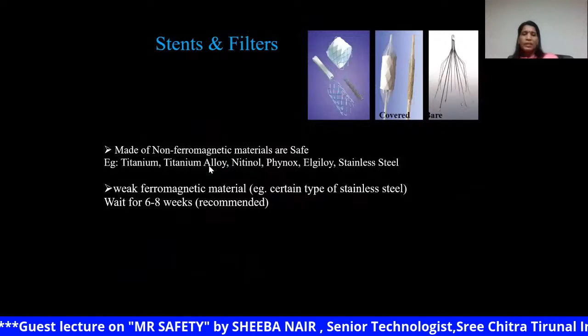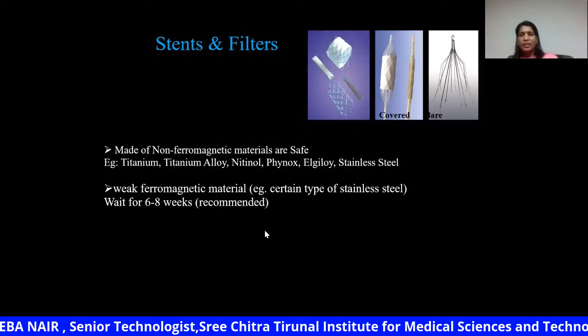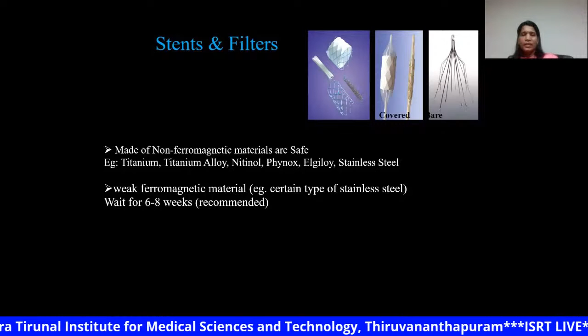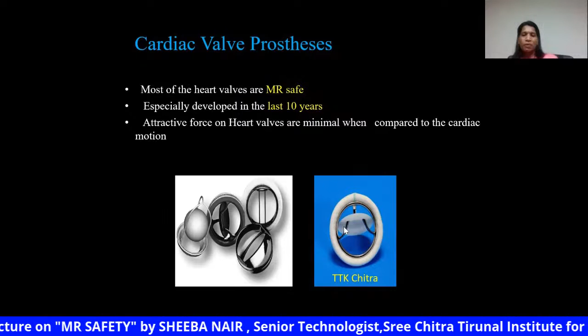Stents and filters are mostly MR conditional, and for most of them we can do MR scanning. If not urgent, we can wait 6 to 8 weeks. Most cardiac valves are safe for MRI. They are conditional up to 3 Tesla, because even though the magnetic field will exert a small force on them, compared to the heart's force it will be less. So it is safe to scan a patient with a cardiac valve prosthesis at 1.5 Tesla or 3 Tesla.